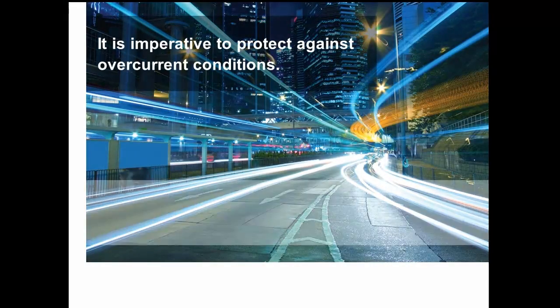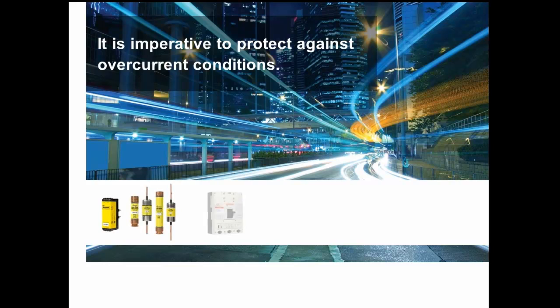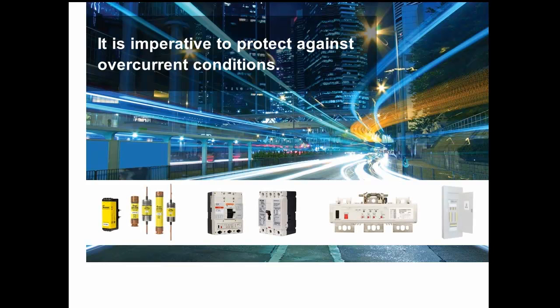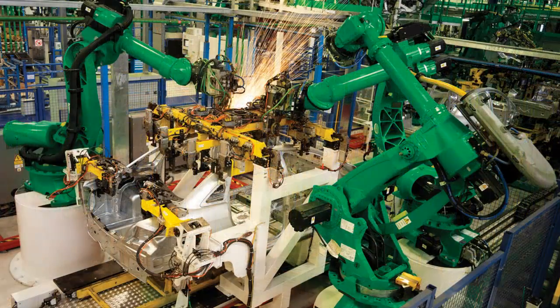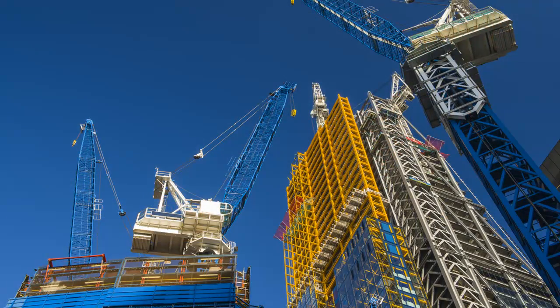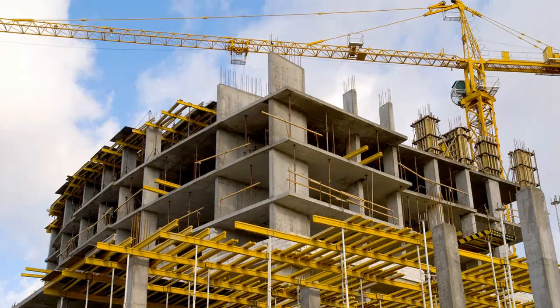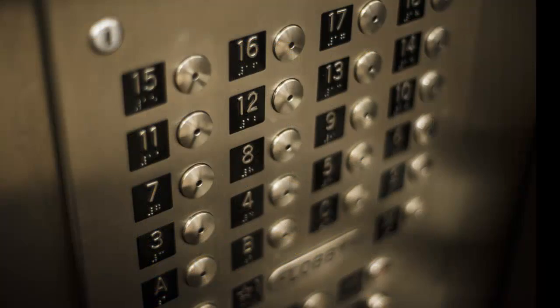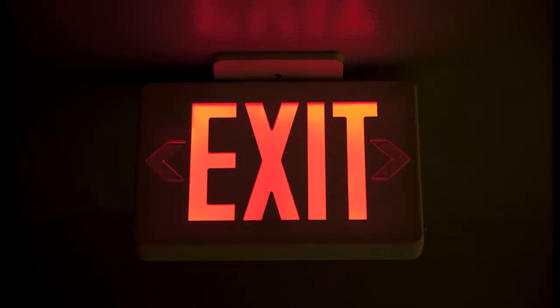Electrical distribution equipment is designed to provide protection against overcurrent conditions. Some circuits in the system supply critical loads to a facility, such as life safety systems, IT equipment, or others. It's imperative that these loads remain energized if an overcurrent condition occurs elsewhere in the critical system. This can be achieved by selecting and installing overcurrent protective devices that are selectively coordinated.